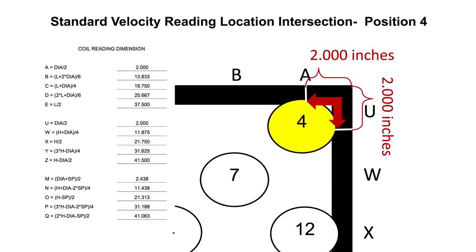Use this method referencing the coil reading dimensions for each standard velocity reading location. For position 4, a measurement and marking for A is 2 inches from the right towards the center, and for U, 2 inches from the top towards the bottom. Therefore, the position 4 standard velocity reading location is at the intersection of A, 2 inches from the right to center, and U, 2 inches from top to bottom.